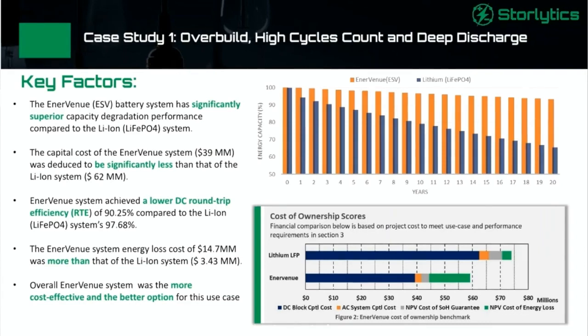Another impact is that the Enervenue system did have a lower round trip efficiency, around 90% compared to 97% for lithium. And this is DC to DC round trip, for a C/4 case.